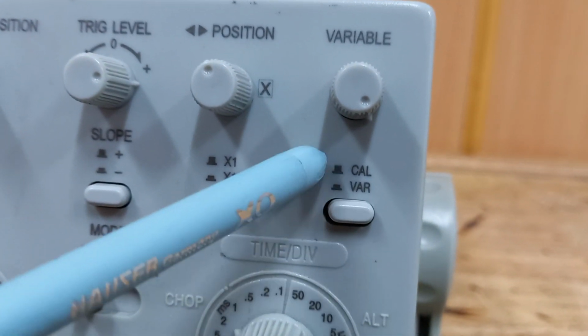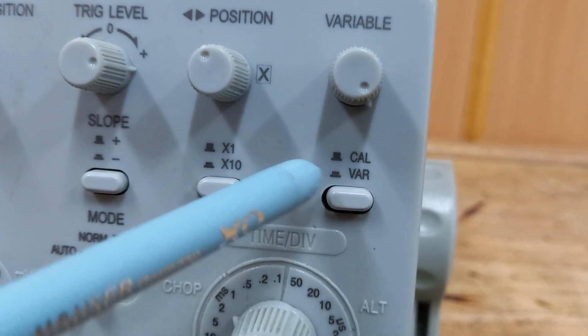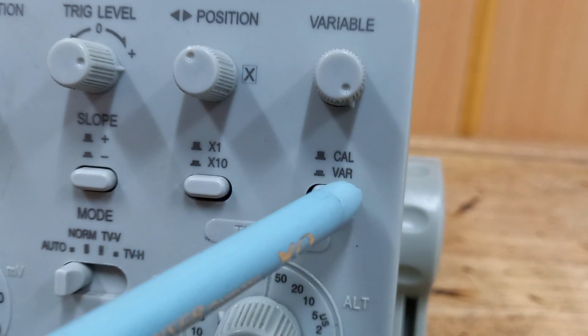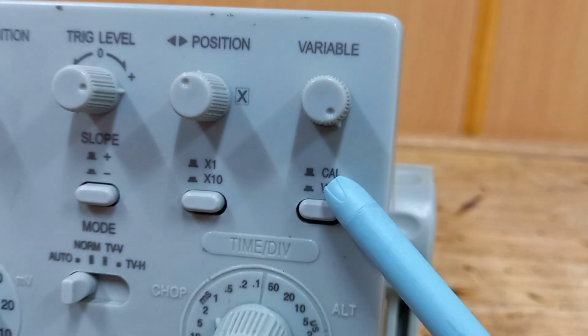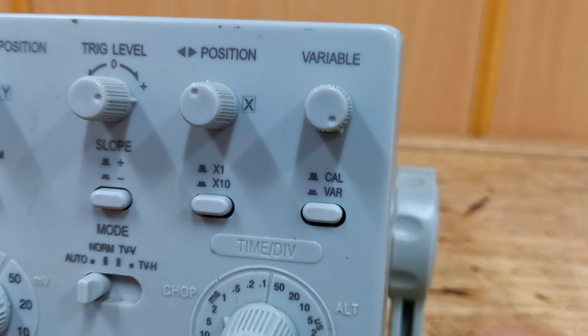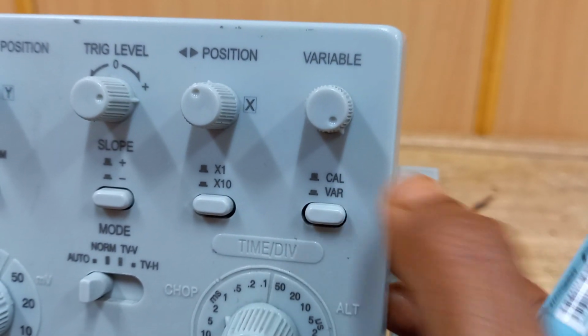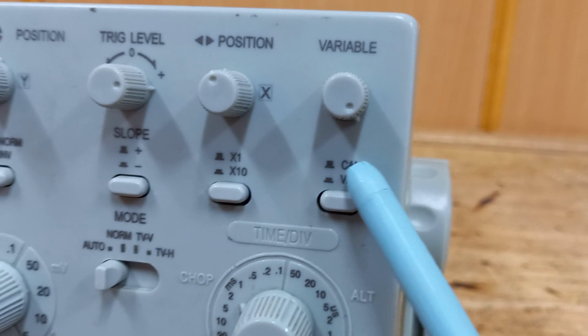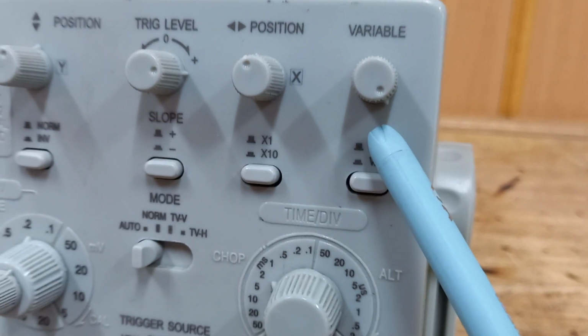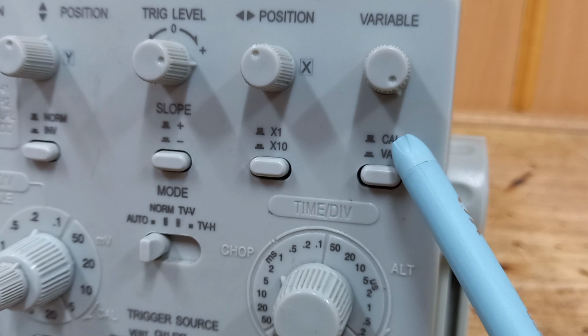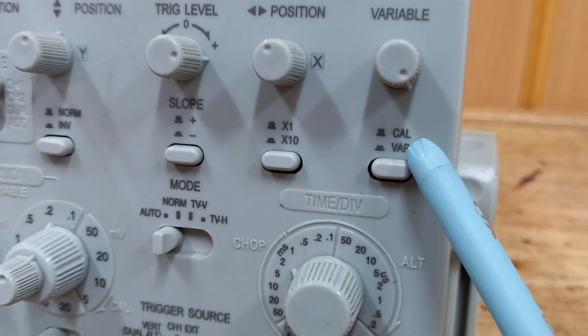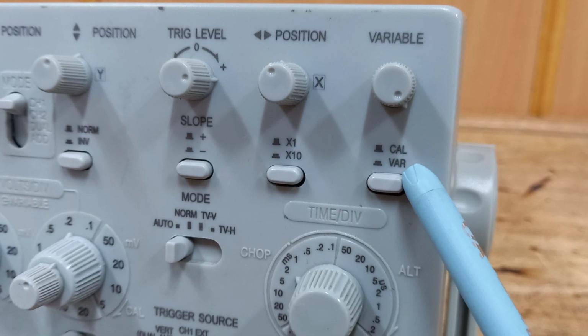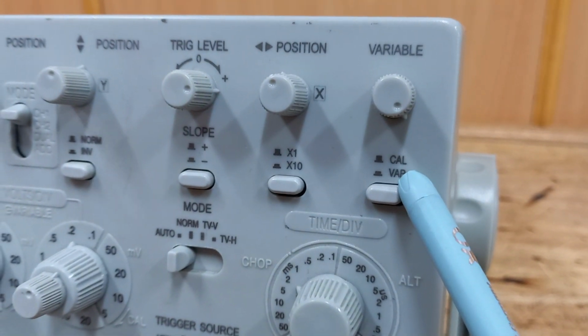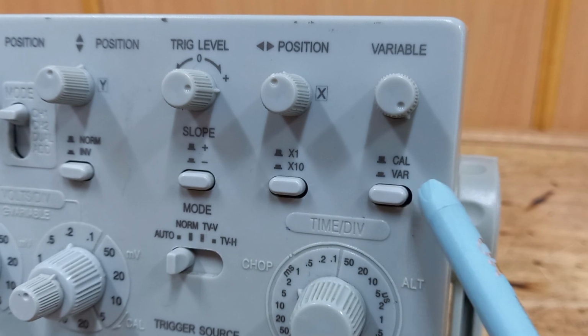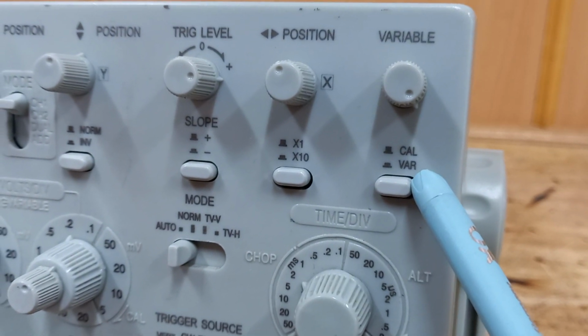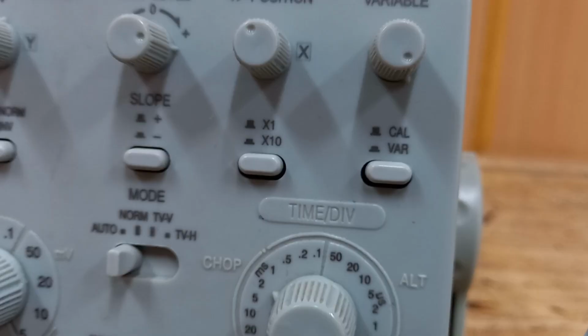There are two options here. One is calibration and another one is variable. If you press inside, the bottom function will be selected. If your knob is outside, the upper function will be selected. Now I'll explain what CAL is. CAL stands for calibration. The calibration option is used for calibration purposes. Calibration involves adjusting parameters such as voltage gain, frequency response, time-base accuracy, etc., to match known reference standards.